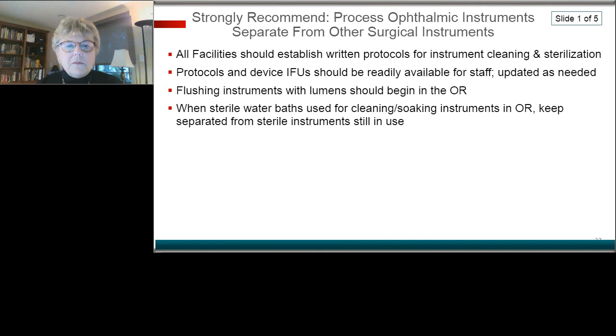Flushing instruments with lumens should begin in the operating room, and this is an emphasis where that teamwork can also be a huge help. Just understanding how important it is, the sooner they can rinse out the lumen, the sooner they can wipe off any of the debris before any drying occurs, makes a huge difference in the overall outcome. When sterile water baths are used for cleaning and soaking instruments in the operating room, keep them separated from the sterile instruments still in use. You don't grab the wrong one. When flushing the lumens, make sure the effluent goes into a separate area so that you aren't putting it back. There's a lot of times that they'll take it in, push it out, take it in, push it out, realizing they are flushing the lumen, but each time they're increasing the concentration of dirty water, basically, with what's coming out of the lumen. So make sure that you're pushing it out into another separate container.